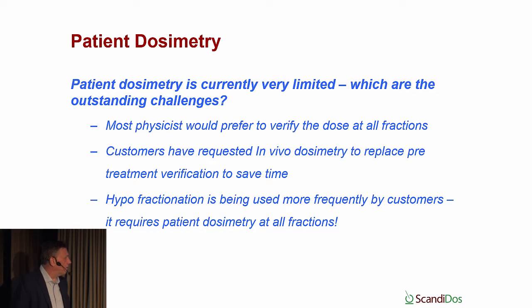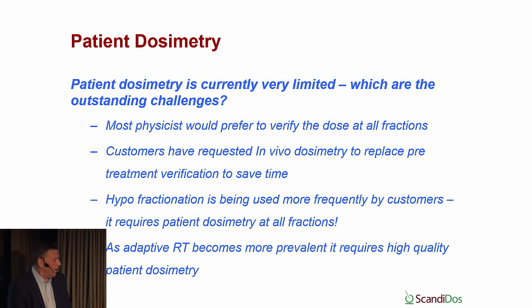Another thing that we were told was that now that hypo fractionation is being used more frequently by our customers, it requires patient dosimetry at all fractions. Because if you're delivering the treatment in very few fractions, each fraction becomes even more important, it has to be 100% correct, and then you really would like to perform QA on it. As adaptive radiotherapy becomes more prevalent, it requires high quality patient dosimetry. You know that adaptive radiotherapy is really around the corner, and if we want to perform it the way it should be, we should take care of the patient positioning, the organ positioning, but also the dose delivered to the patient.